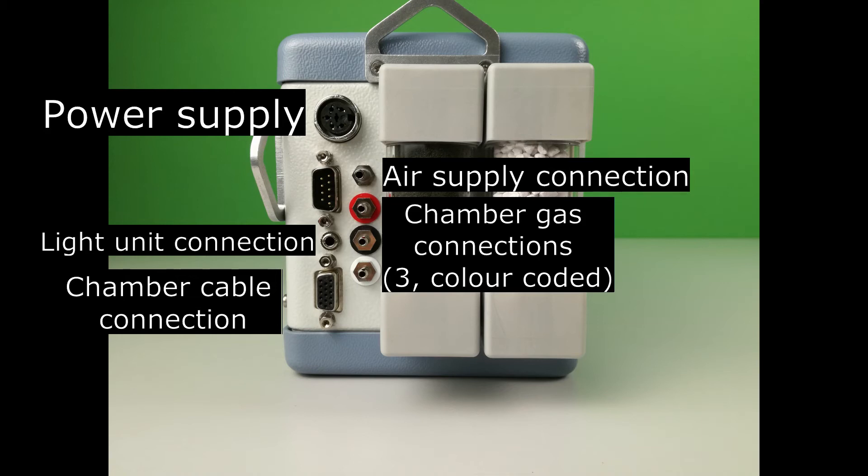On the right at the top is the air supply connection. Fresh reference air is taken in here. It is vital that incoming CO2 concentrations are stable.